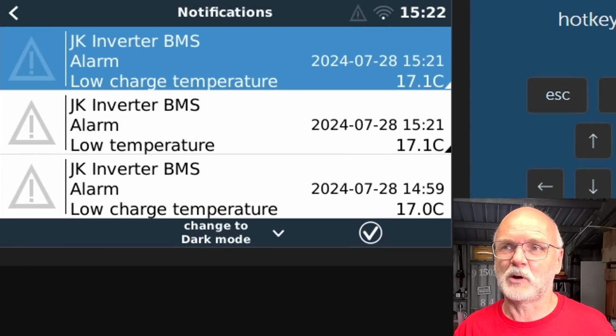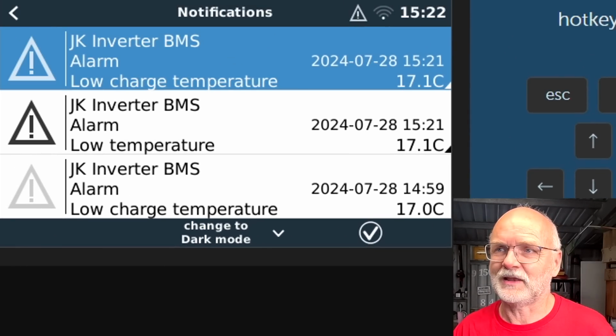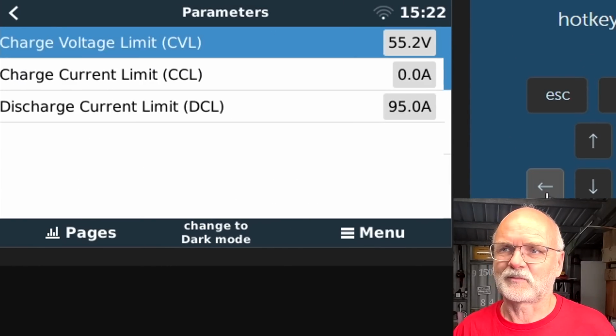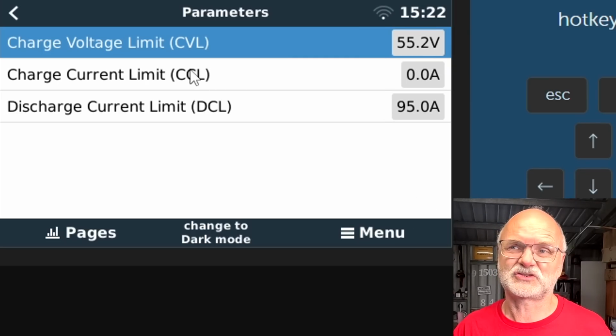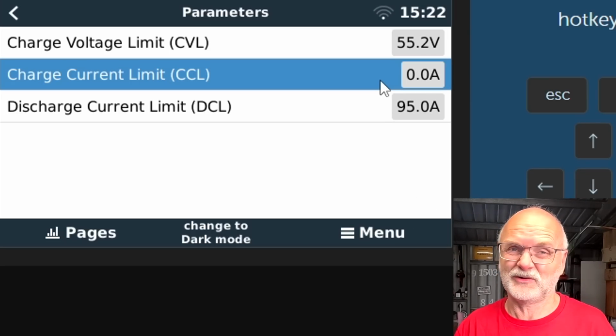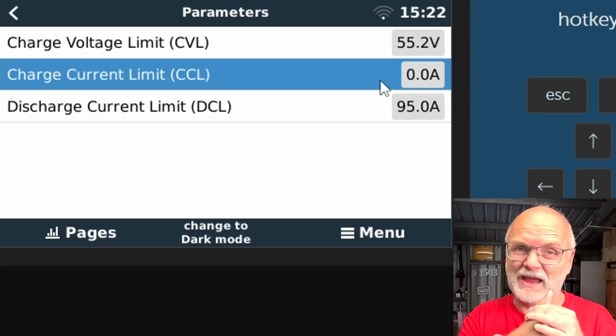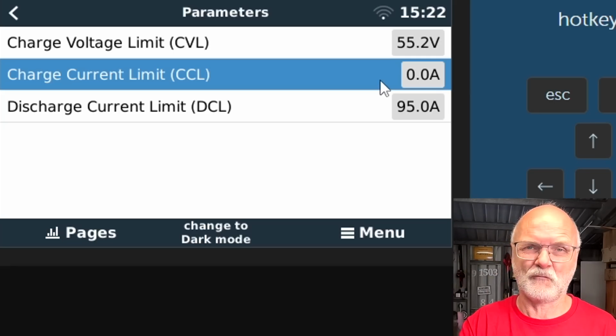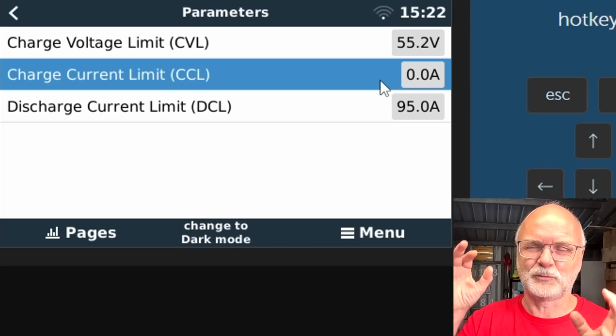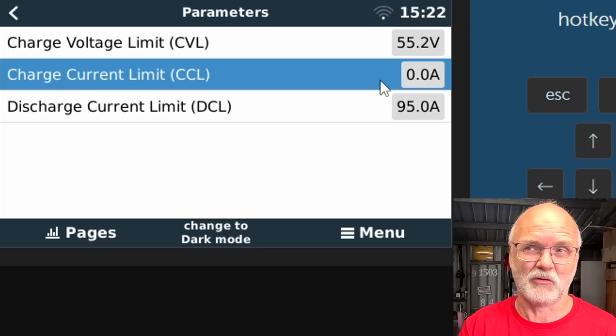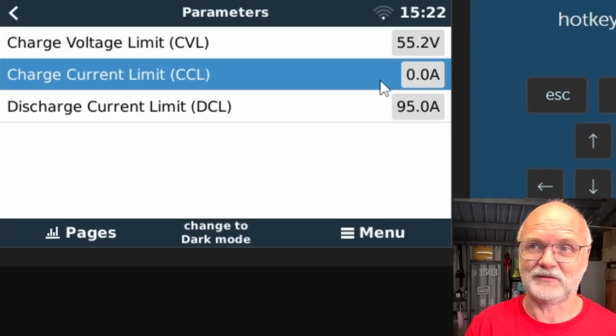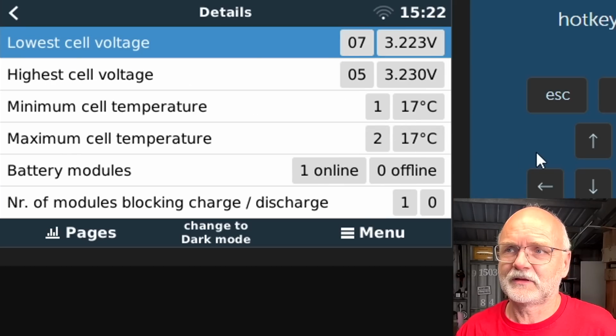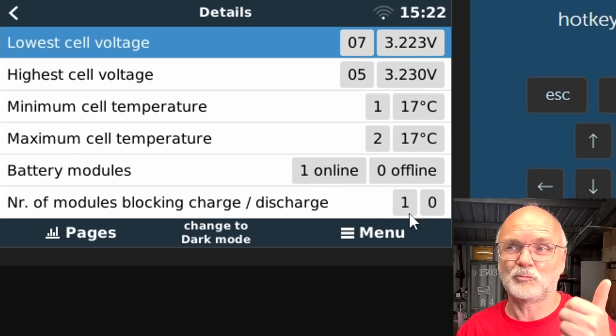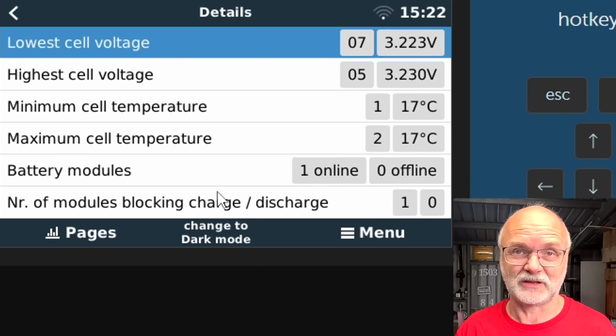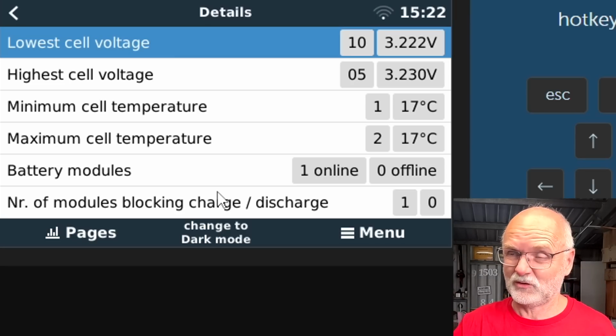So if we have a look in the remote console and confirm this alarm here, so it stops beeping, we can see we've got a charge current limit now of 0 amps because there's only one battery and this battery has an issue: over voltage, over current, over temperature, under temperature. Regardless what it is, it will set your charge current limit to 0 or your discharge current limit respectively. And if we go into details, we can see we've got one battery and one battery is actually blocking charging. I still can discharge this battery, of course, there's no issue.